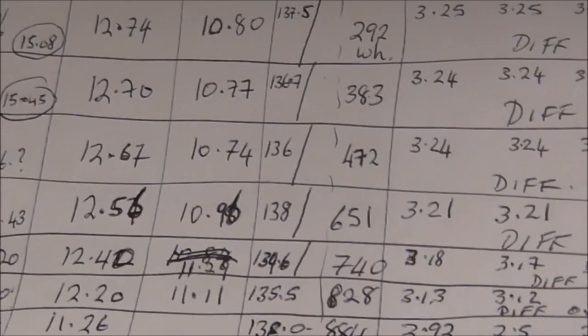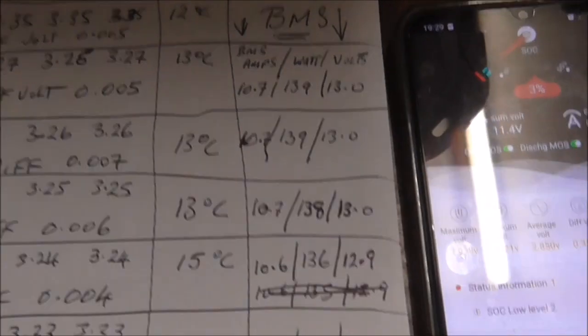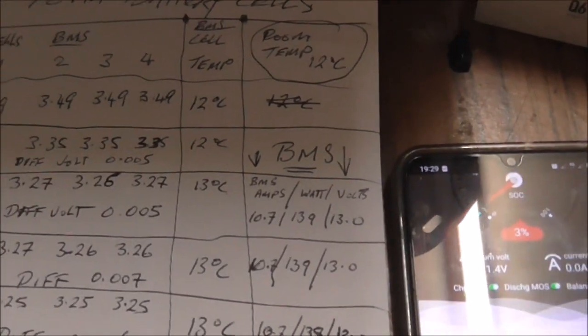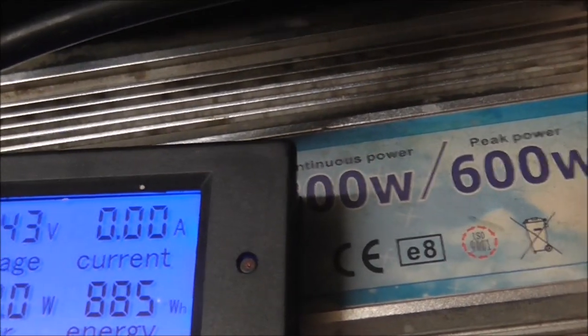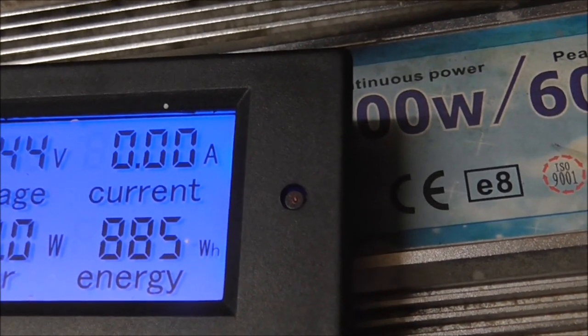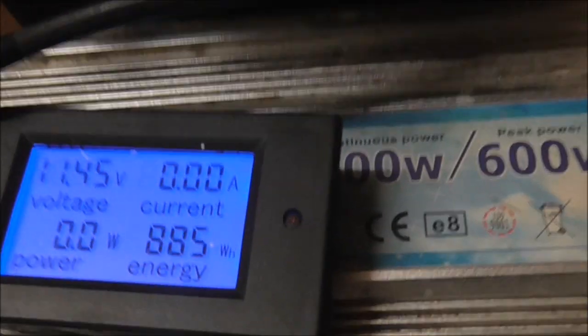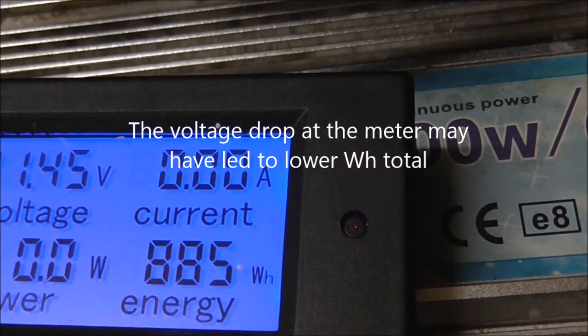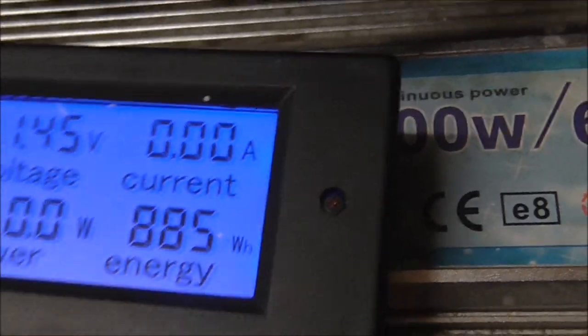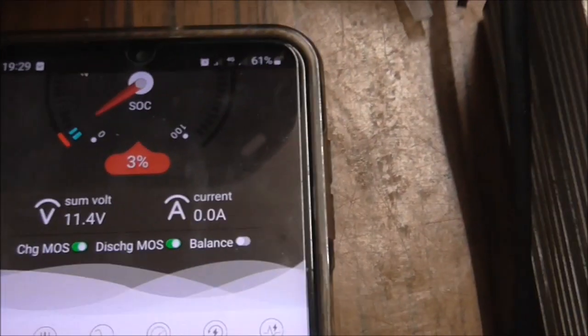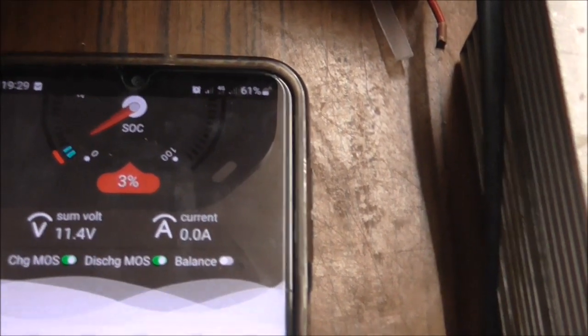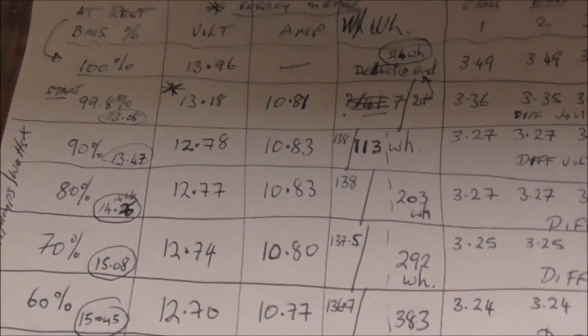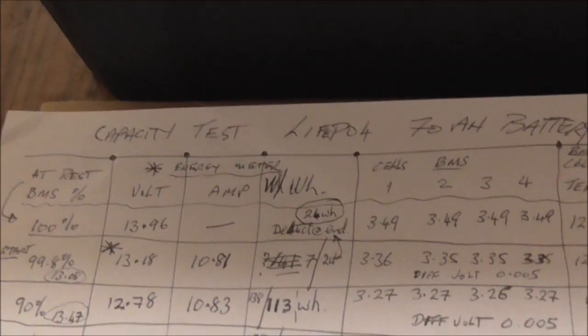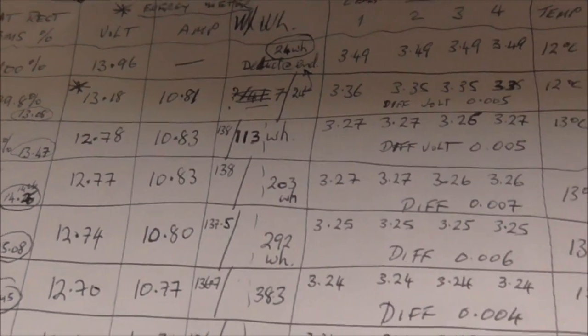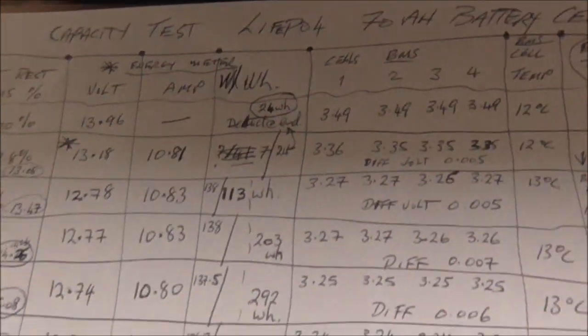So therefore I reckon 6.5 hours, taking an average of 10.7 amps, the 70 ampere hours is there alright. Taking off the 24 that I had on the meter, that's about 860, and the total energy in the module should be 896, and clearly there's more energy there because I'm not down to 10 volts. So I'm happy - I can't see me going below 60% normally.